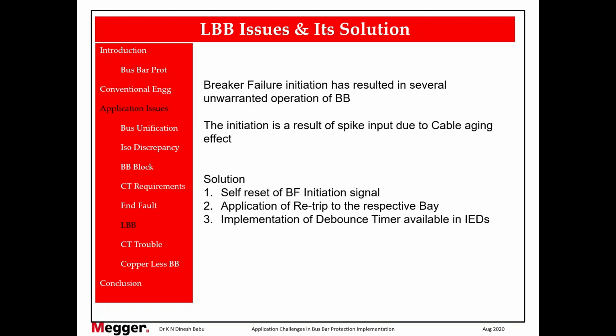Another solution: implement a debounce timer. This is a beautiful feature because it's hardly 5 seconds of work. If you have a numerical relay, there is already an option called debounce timer available. What is a debounce timer? It is the duration for which the input will not be sensed. For example, you gave an input high. If my debounce timer is configured as 10 milliseconds, the input has to be high for more than 10 milliseconds. Only after that will the input be sensed as high. So all numerical relays should have this. You just enable that to 10 milliseconds or 15 milliseconds. Then it will address this.